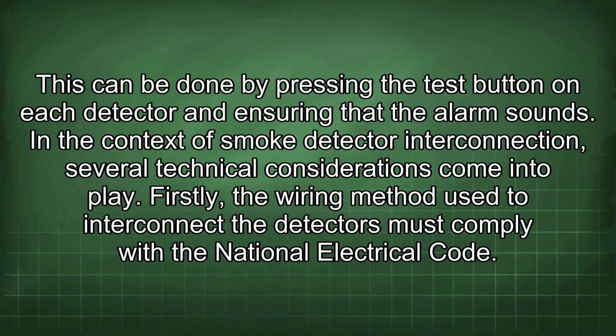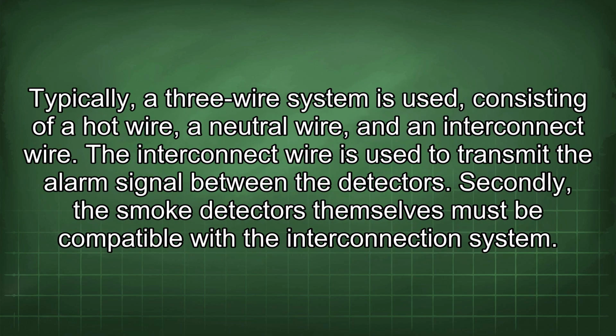In the context of smoke detector interconnection, several technical considerations come into play. Firstly, the wiring method used to interconnect the detectors must comply with the National Electrical Code. Typically, a 3-wire system is used, consisting of a hot wire, a neutral wire, and an interconnect wire. The interconnect wire is used to transmit the alarm signal between the detectors.